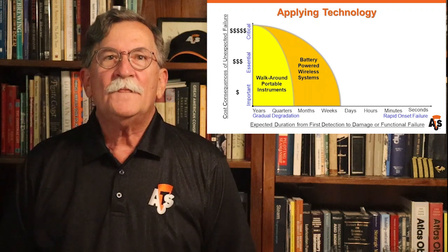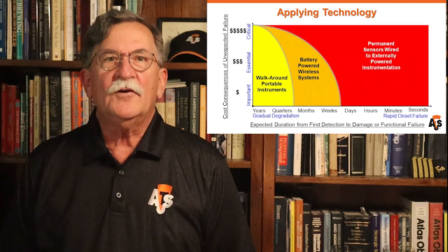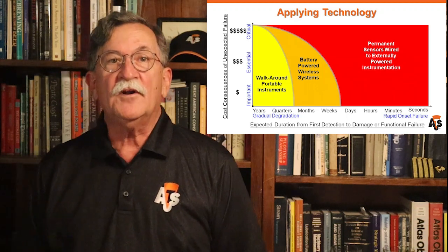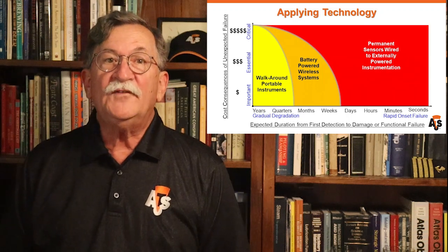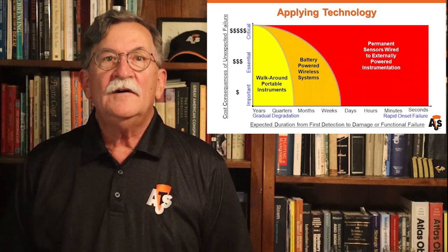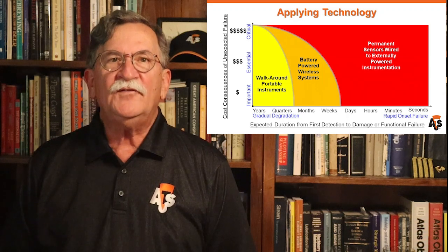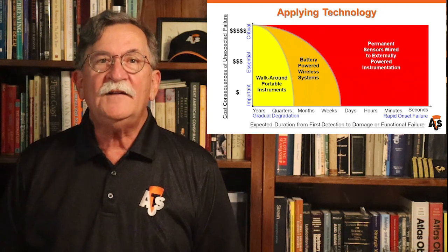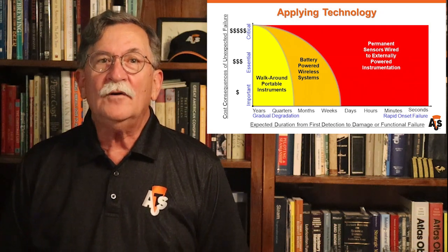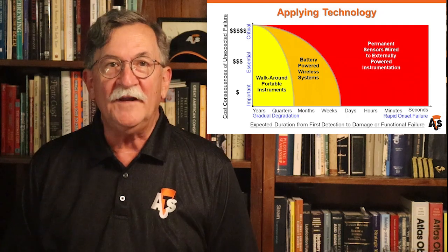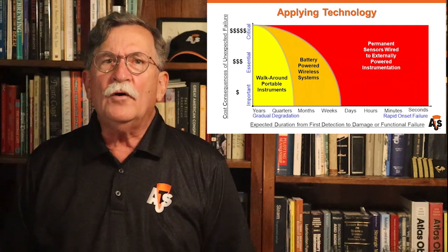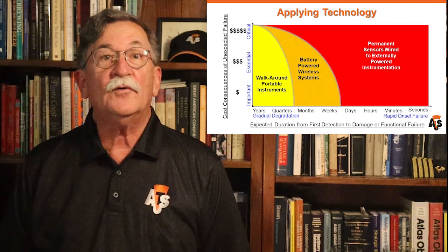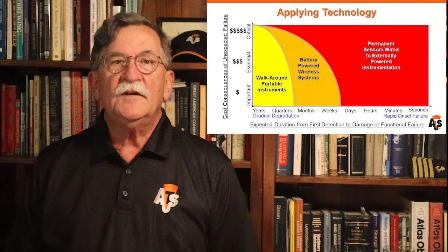Higher value machines, on the other hand, in terms of the cost consequences of their loss and criticality to production, or they progress to failure in a week or less, should be monitored with permanently mounted sensors wired to permanently powered instruments that are capable of collecting data on the order of every hour to as quickly as every minute. Of course, all this data needs to be sent to a central software or dedicated remote monitoring center for evaluation so that timely recommendations can be made.